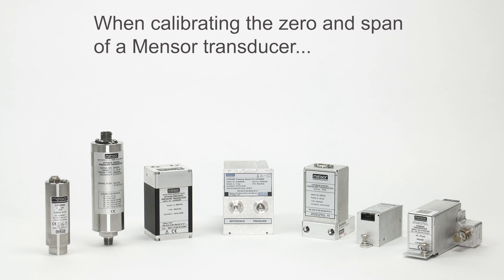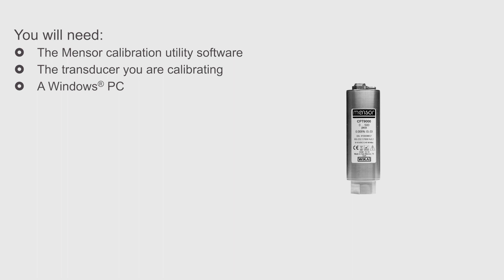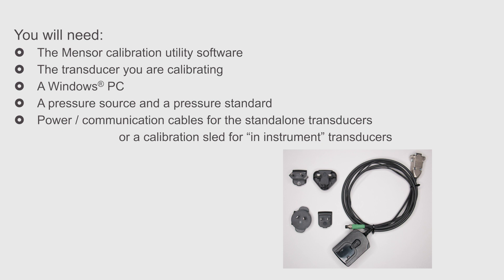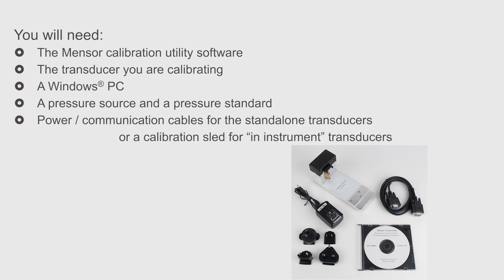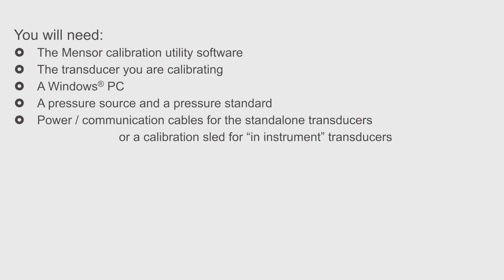Calibrating the zero and span of any Mensor standalone transducer or a transducer used inside an instrument will require the Mensor calibration utility software, the transducer to be calibrated, a Windows PC, a pressure source, a pressure standard, the combined power and communication cables for standalone transducers, or a calibration sled for transducers that are a component of a Mensor pressure controller or indicator.